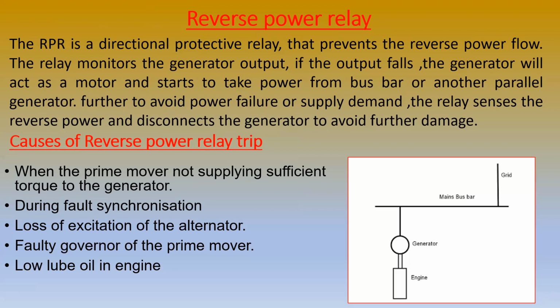So when the generator is providing power supply to the main bus bar, we can meet the demand. Suppose the generator cannot supply power to the bus bar because the main torque is becoming less than the friction losses torque. If it becomes less, it starts to take power from the bus bar instead of providing power to it, and it will act like a motor.